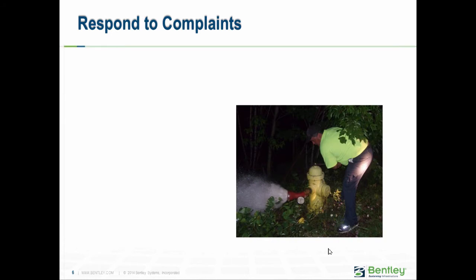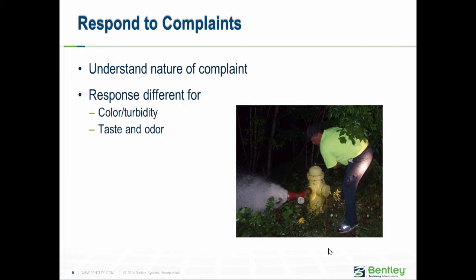Responding to complaints is a tough problem because you need to understand the nature of the complaint. If the water tastes bad, we need to focus on moving water quality along. If it has turbidity, we need to understand why that turbidity occurred. The response will be different for color and turbidity — which involves increasing velocity — versus taste and odor problems, which means bringing high-quality water into the problem area. In addition, you need to develop a history of chronic problem areas and use that history to do a better job planning flushing going forward.